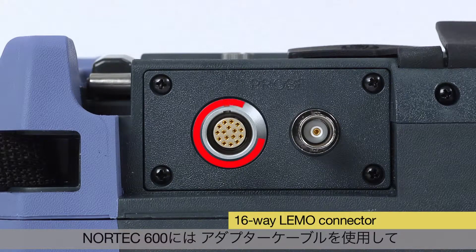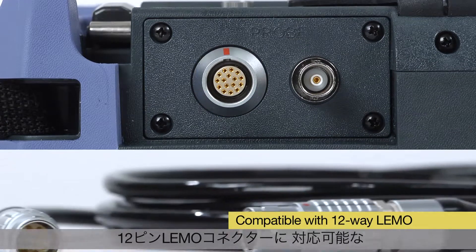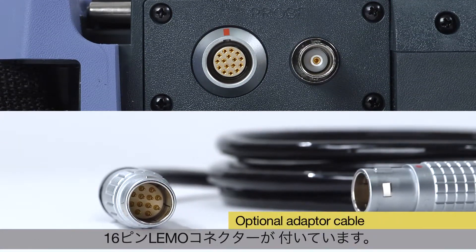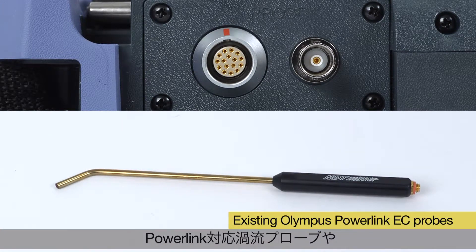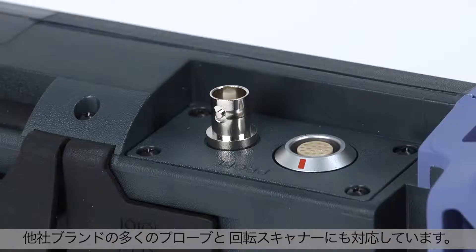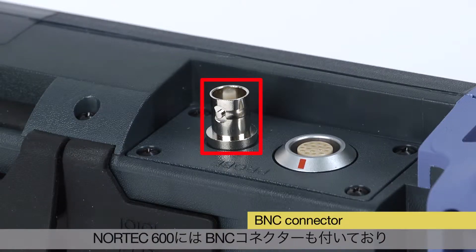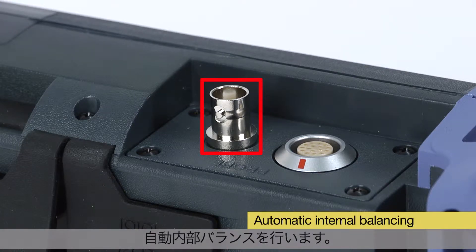The Nortec 600 features a 16-way LEMO connector that maintains compatibility with 12-way LEMO connectors by using an optional adapter cable. It also maintains compatibility with existing Olympus Powerlink eddy current probes as well as other major probe and scanner suppliers. The Nortec 600 also features a BNC connector with new automatic internal balancing for single-coil absolute probes.